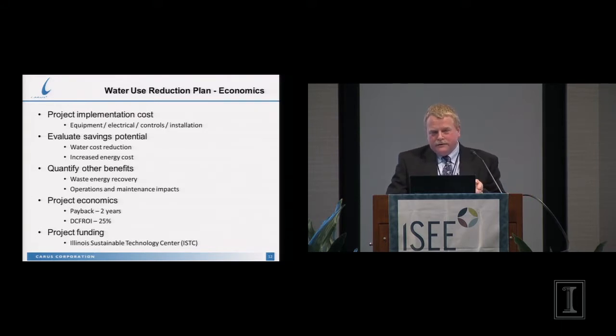But if you combine the chiller with a cooling tower, in the winter it gets cold - I won't need to run the chiller, I won't even have to run the fans on the cooling tower. So that energy cost calculation can get pretty complicated, and it's worth doing, because it may make the economics of your project. If you just assume you're going to run that chiller all the time, the economics are going to look pretty bad. But if you realize you only need to run it for three months in the summer, then off and on for a few more months, and then leave it off, it changes things drastically.